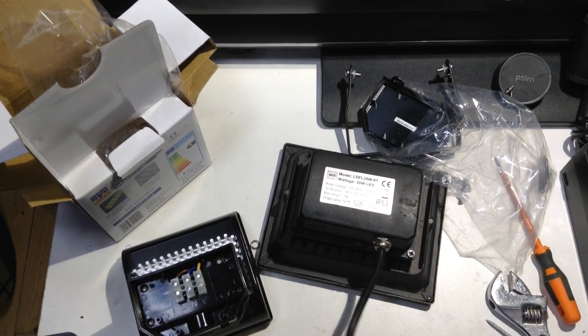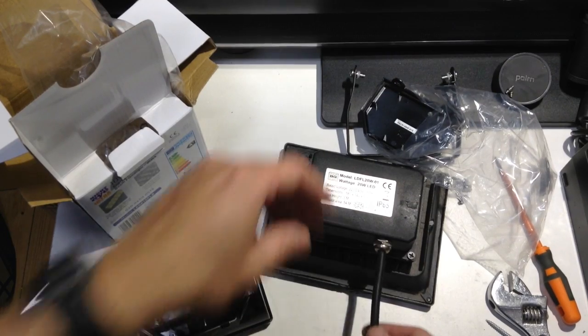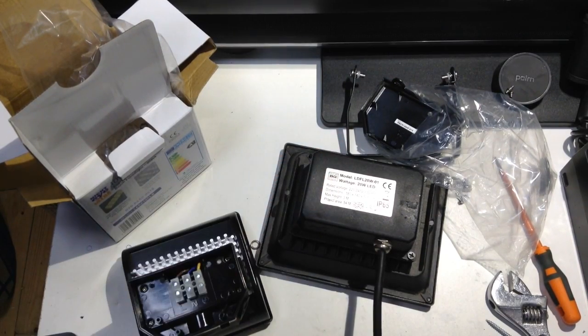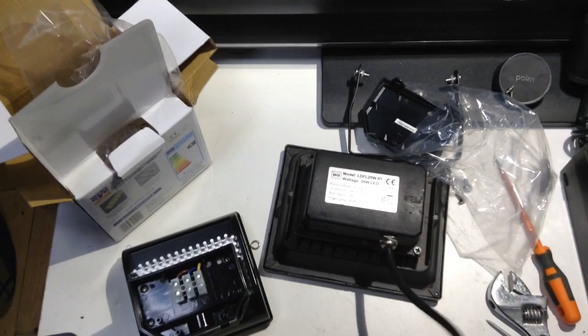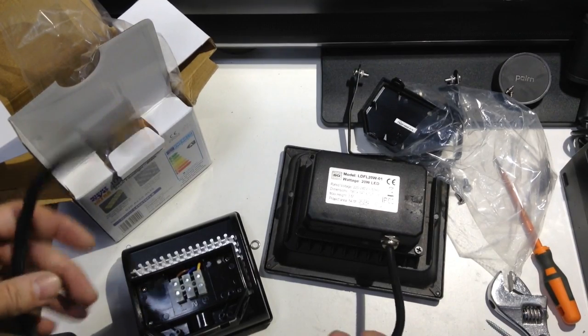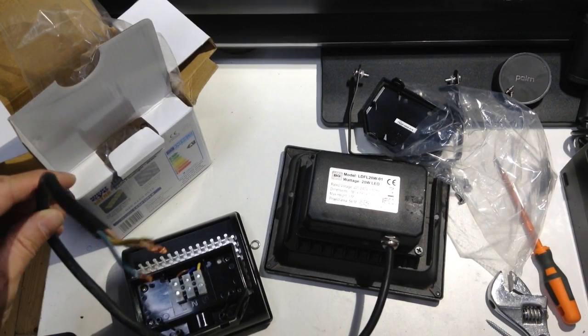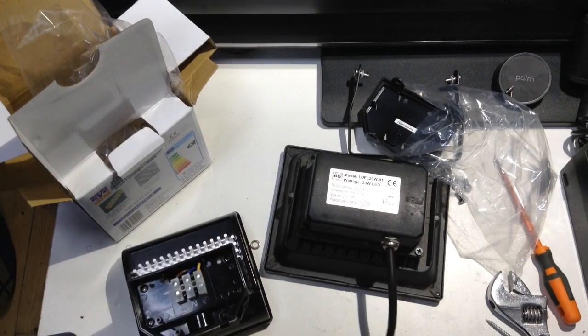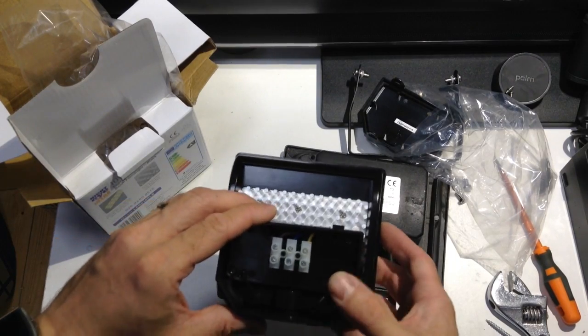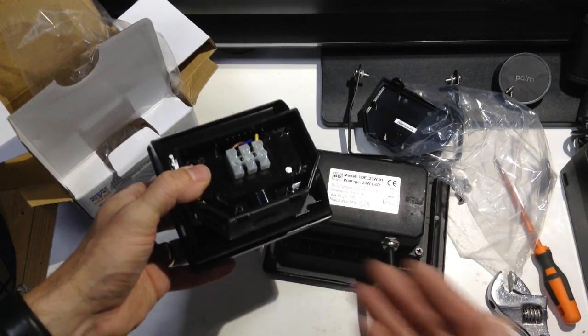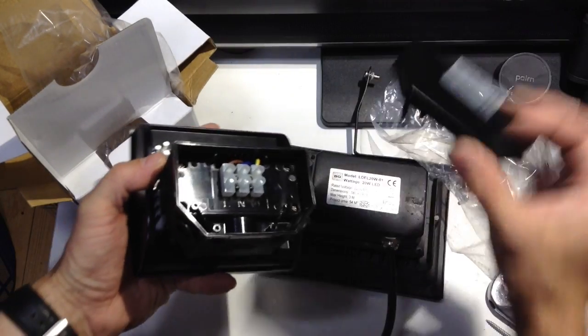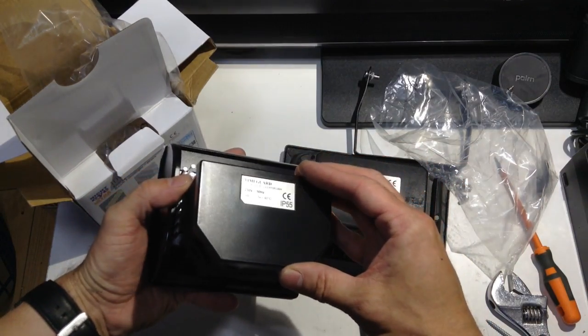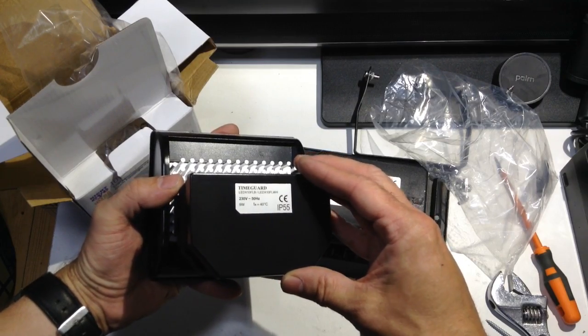So moisture's not going to give it too much of a headache anyway, even if it did get a bit damp in there. So they really didn't need to bother going to the lengths of pre-wiring it. They could just as easily have provided a terminal block as TimeGuard have done here. So I can take my existing wire and terminate it directly into there, and then of course enclose it off with the cover to maintain its IP rating.